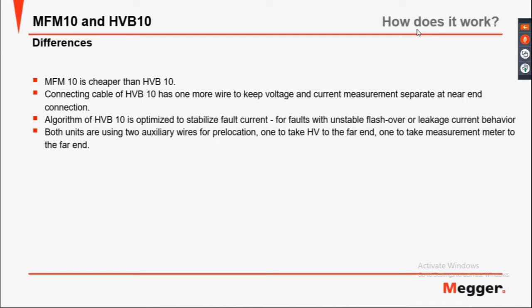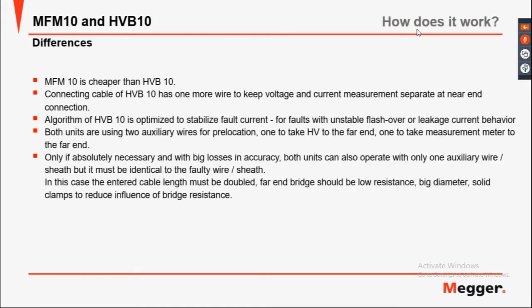Both units use two auxiliary wires for pre-location: one to take the HV to the far end and one to take the measurement meter to the far end. Only if absolutely necessary, and with big losses in accuracy, both units can be operated with one auxiliary wire, but it must be identical to the faulty wire sheath. In this case, the entered cable length must be doubled. The far end bridge should be low-resistant, big-diameter, solid clamp to reduce influences on the bridge resistance.